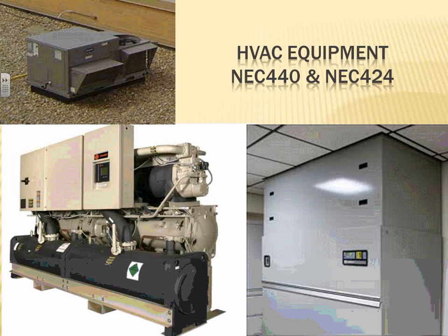So the way I understand the HVAC equipment, guys, we have heating. So I thought to pick up the article that talks about heating, article 424, which covers fixed electric heating. That relates to electrical heating equipment, where you burn electricity to get heat, not gas, not natural gas. So article 424 will be your baby if you're doing some heat.